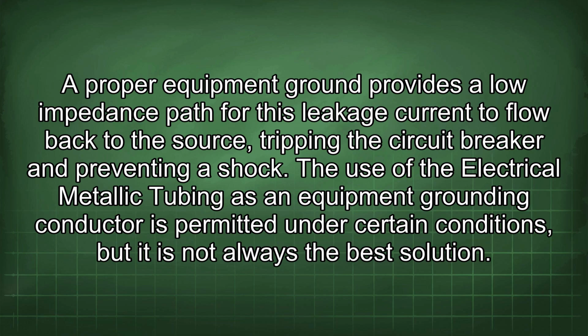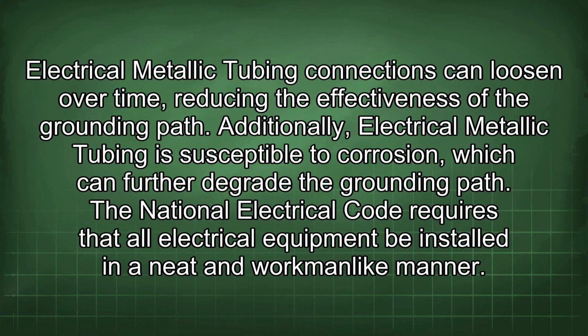The use of the electrical metallic tubing as an equipment grounding conductor is permitted under certain conditions, but it is not always the best solution. Electrical metallic tubing connections can loosen over time, reducing the effectiveness of the grounding path. Additionally, electrical metallic tubing is susceptible to corrosion, which can further degrade the grounding path.